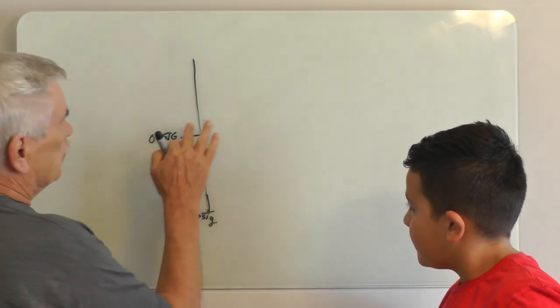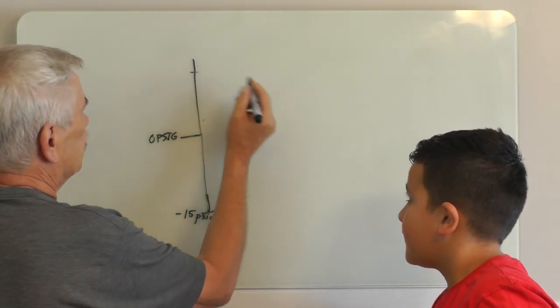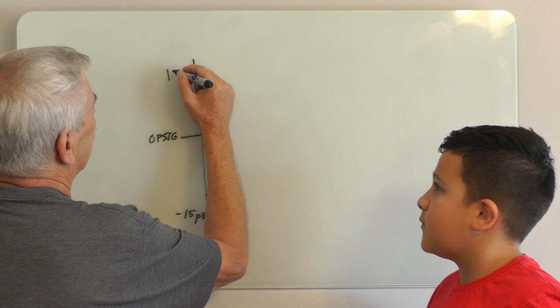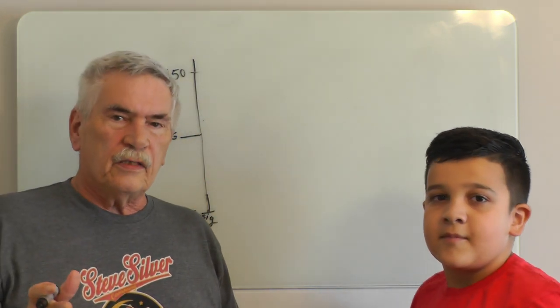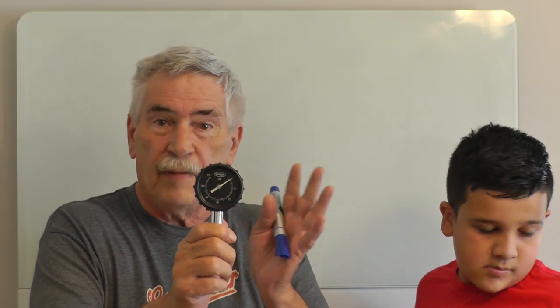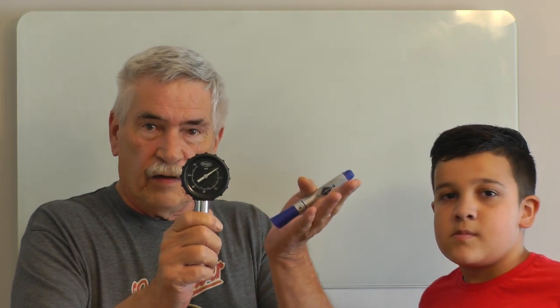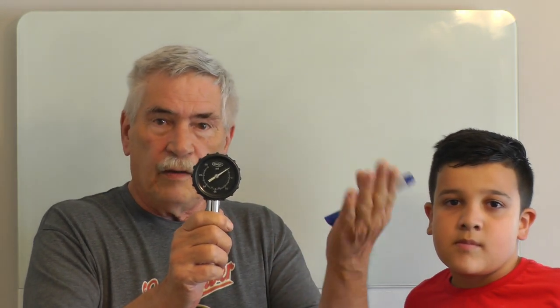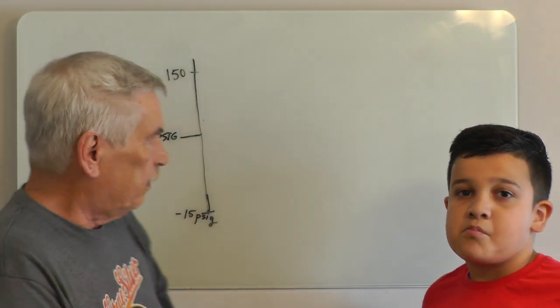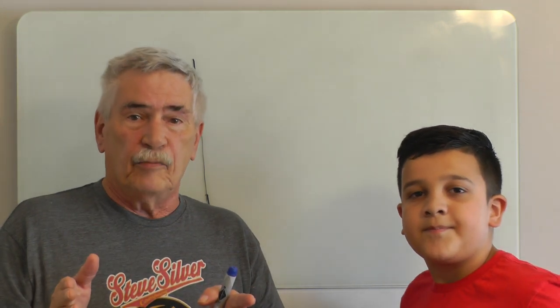Anything above this line is positive pressure; anything below is negative pressure. Let's use an example — say 150 PSI. When you see PSIG, that means gauge pressure. If we take a gauge like this one, you can see the needle is on zero. But we know there's atmospheric pressure around the gauge — it's not measuring that actual pressure. Gauge pressure is measured relative to atmospheric pressure. So if we have 14.7 PSI and subtract that off, we're left with zero.